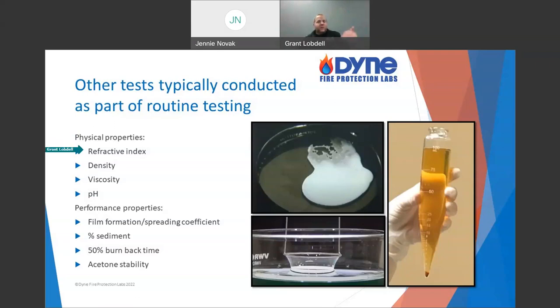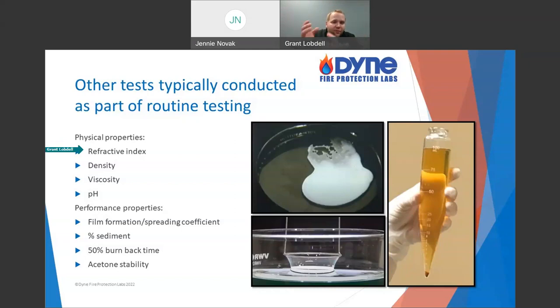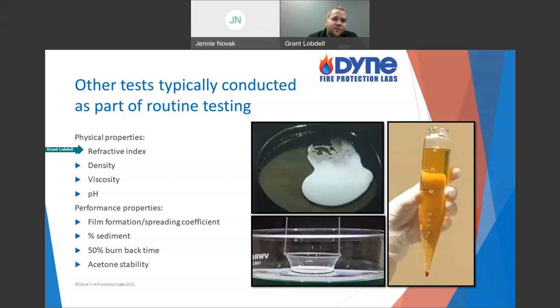To recap the test equipment: for expansion and drain time, we've got the test nozzle and backboard. For spreading coefficient, we use a tensiometer — pull a ring through the sample and measure the force. For all these physical properties, I call it plug-and-chug — you have an instrument, typically a benchtop unit here in the lab, though portable field versions exist. You put your sample in, hit go, and the instrument gives you a number.